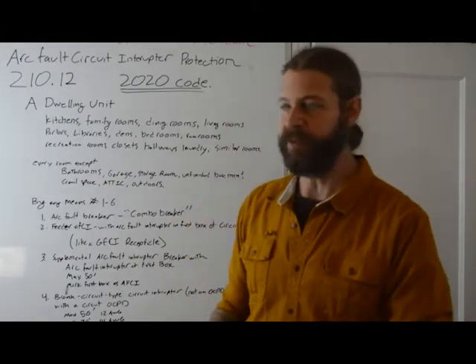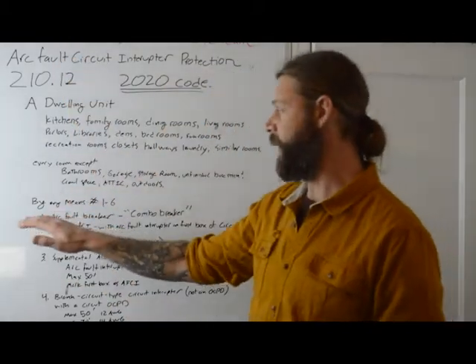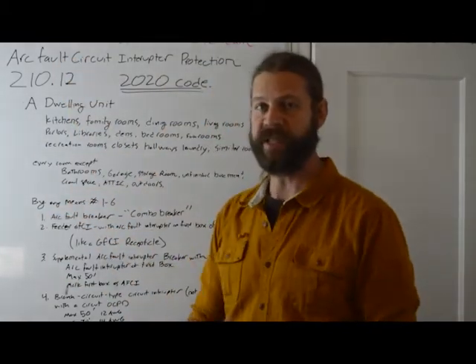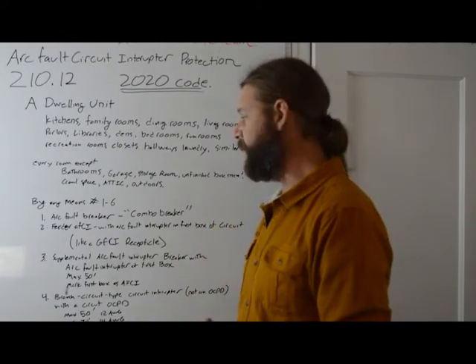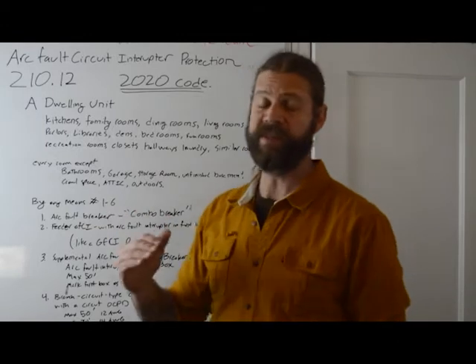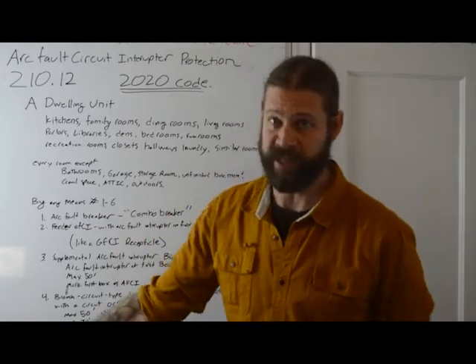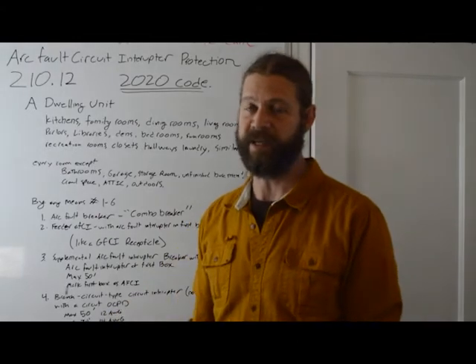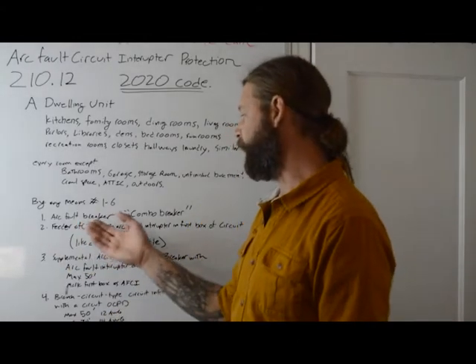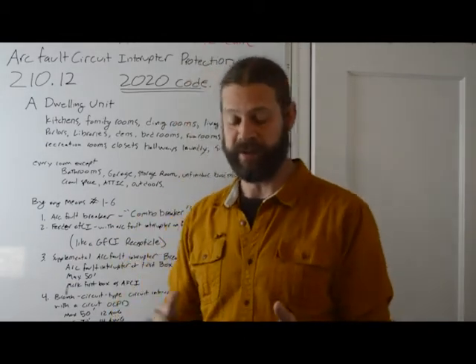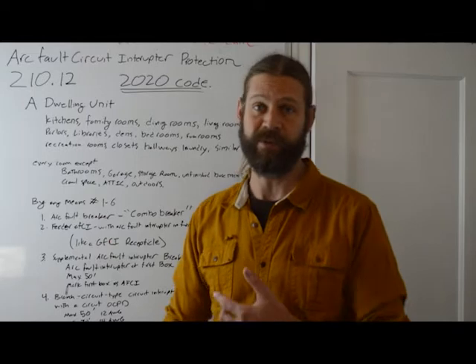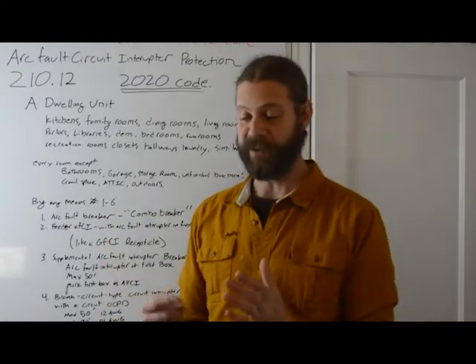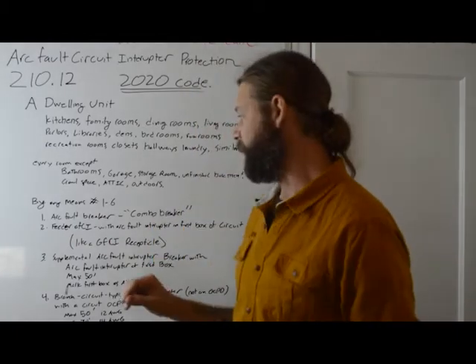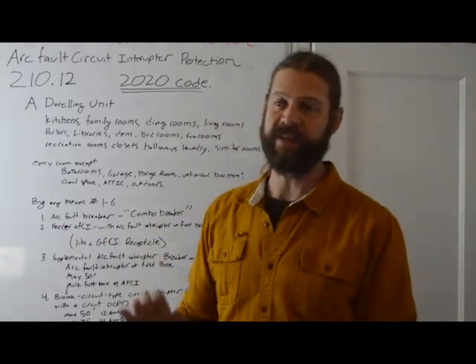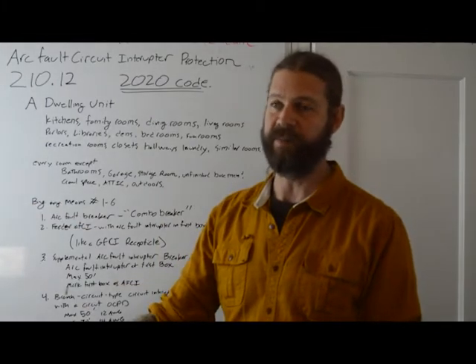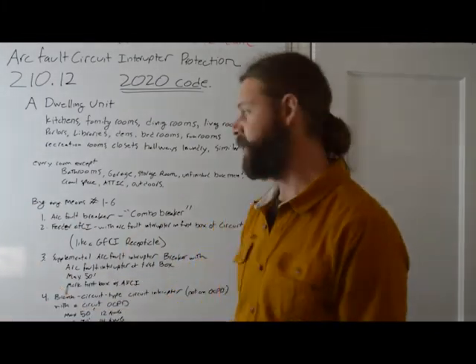And this is a confusing code section because it says you can give it arc fault protection by any one of these means, 1 through 6. And it gives you 6 means of protecting it from arc fault. And one is the most common, and by far, like 98% of all arc fault protection that's installed in new builds is done this way: arc fault combination breaker. So it's an arc fault breaker, it's an arc fault interrupter, and it's an overcurrent protection circuit breaker. And it's a single device. It has a little white wire. We've seen them. We know what they do. That will protect the entire circuit and does not have a length limit. It's the easiest way to do this thing.